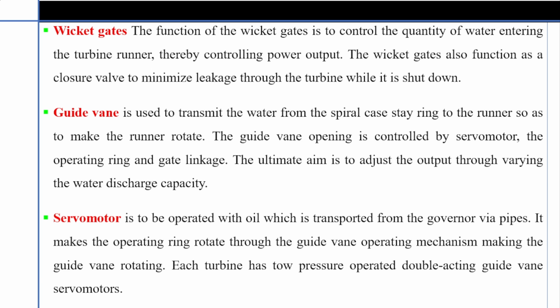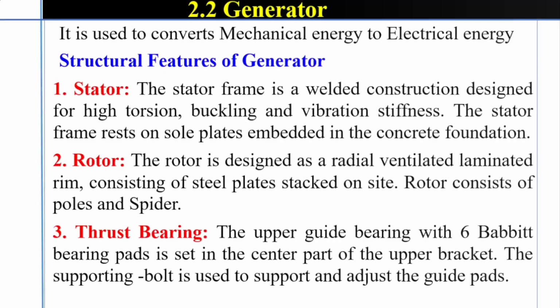The ultimate aim is to adjust the output through varying the water discharge capacity. Servo motor is to be operated with oil which is transported from the governor via pipes. It makes the operating ring rotate through the guide vane operating mechanism, making the guide vane rotate. Each turbine has two pressure-operated double-acting guide vane servo motors.